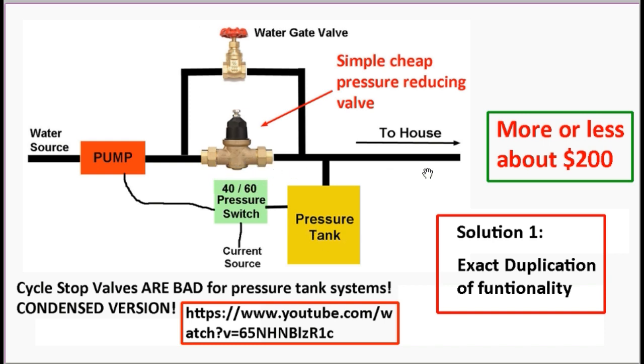Only after you turn off the water does the water dribble through this bypass and go into the pressure tank at a very slow rate and refill the pressure tank. With a cycle stop valve, that rate is preset to about 1 gallon per minute. So even if you have a small pressure tank, this might take 30 seconds or a minute to refill at this slow rate. Now with this water gate valve here, you can adjust the bypass rate. If you adjust it too slow, it will take a long time to refill the pressure tank. And if you adjust it too fast, you might get cycling, which you are trying to avoid because you don't want cycling. It's a cycle stop valve.